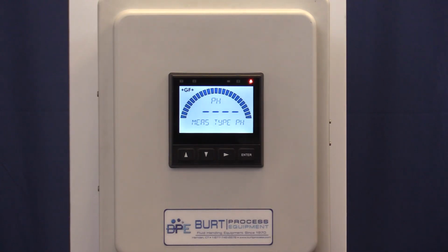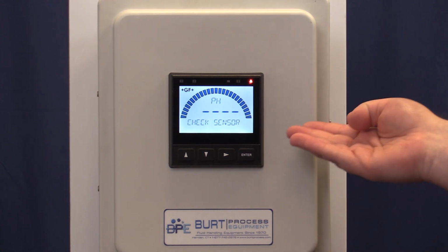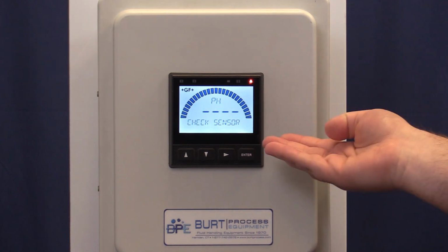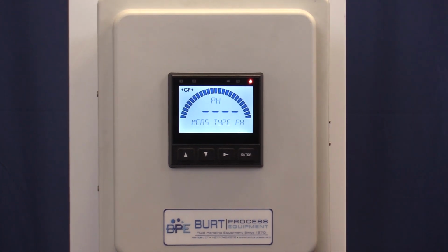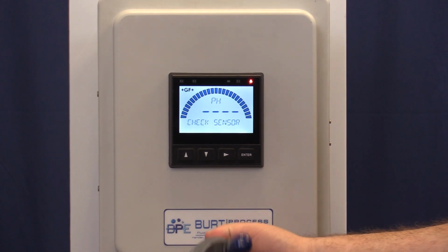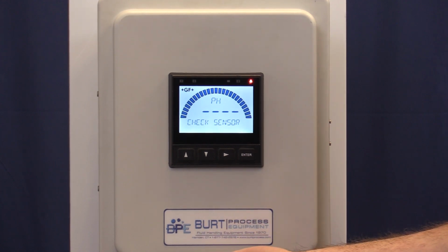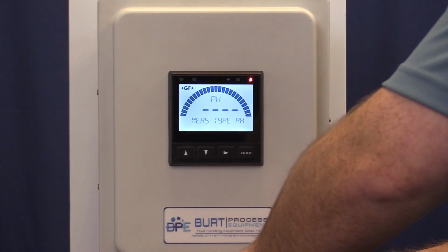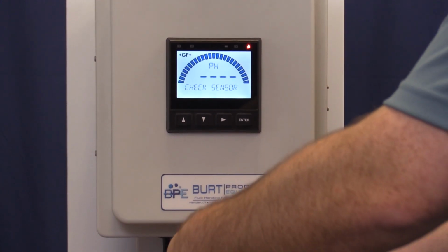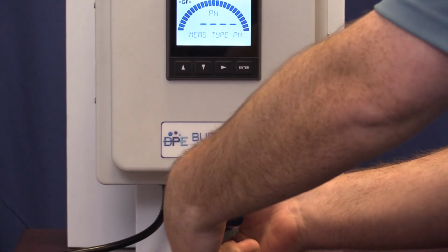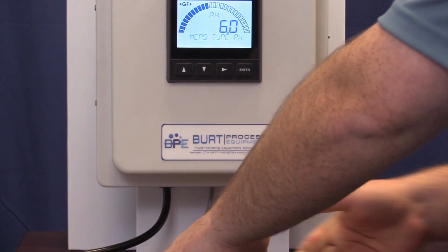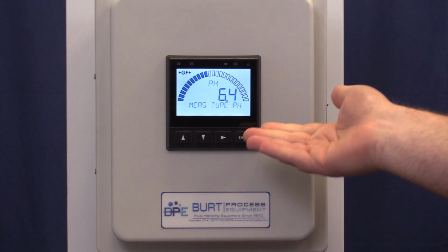So the possible cause is that the 9900 is not talking to the sensor, there's a missing sensor, or the sensor hasn't been properly wired. So as you can see here, we currently have the check sensor error message, and that's because the pH electrode isn't properly tightened up to the 2751 submersible electrode. So if we tighten this up, it should correct the problem. So as you can see, the error message is no longer there.